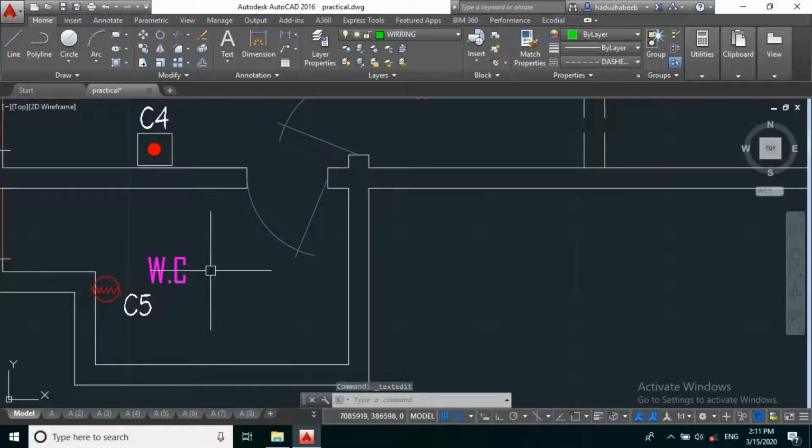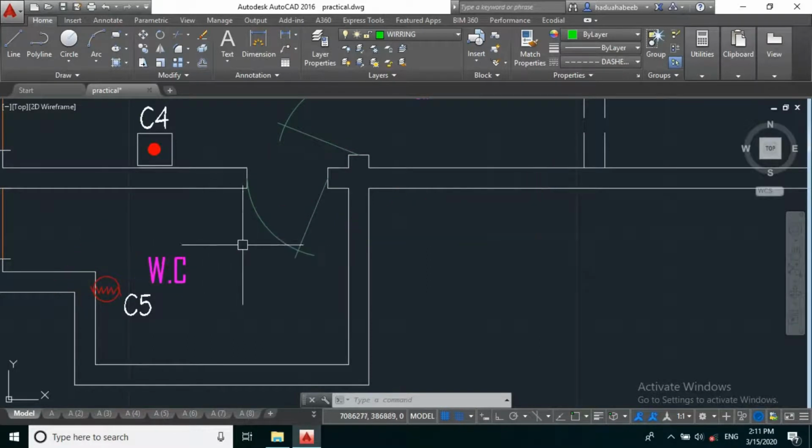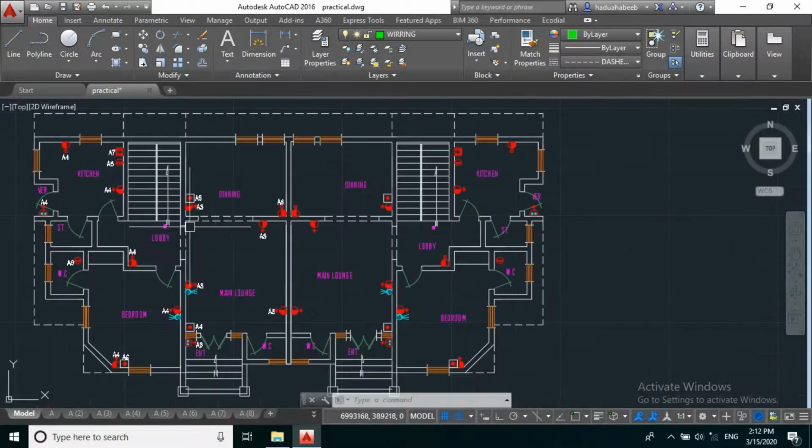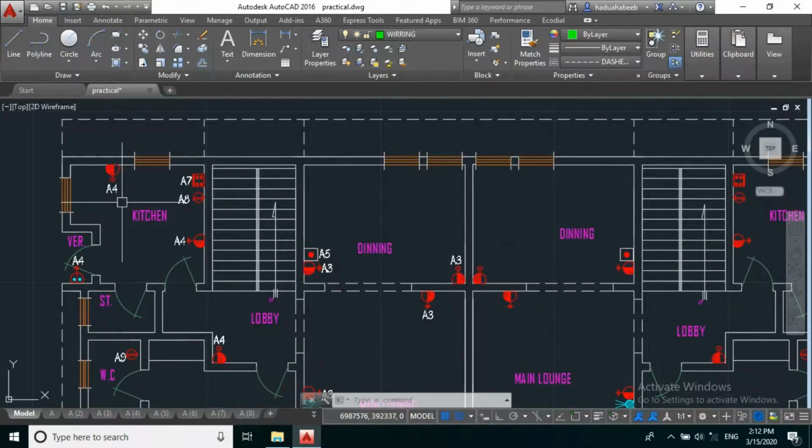So this is how we distribute our electrical load, and we are yet to consider the low power. Generally, for a residential project, having a single circuit for the entire low power system is enough. And for future growth, based on IEC standards, 20 to 30% of the total load estimate is required. So hope you gained a lot in this video. In our subsequent classes, we'll be looking into the load estimate.